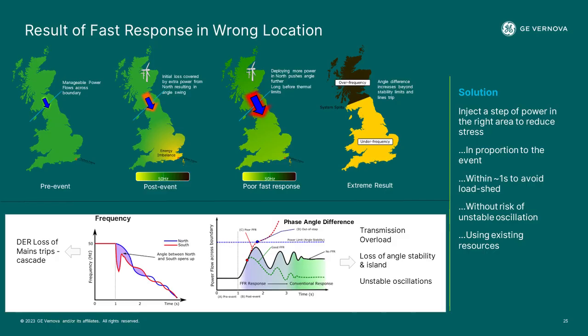In this example, which is the Great Britain system, what I'm illustrating here is, there was an interconnector loss, which caused the frequency to drop. Now, in this case, we used generation pickup in the north to bring frequency back to normal and balance the supply and demand. But because we did it in the north, it caused additive stress across the system because the loss was down in the south. And so the angle separation between the north and the south increased even though we were restoring frequency. And as a result, the system separated.